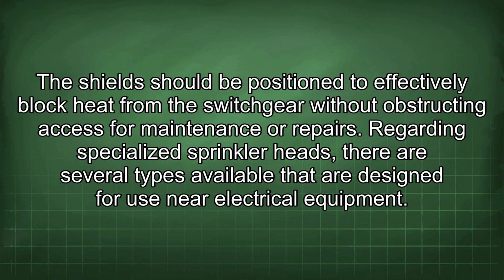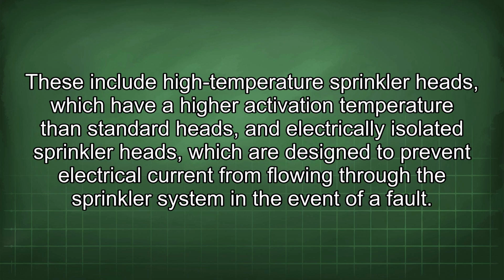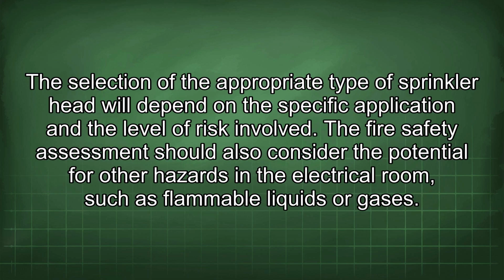Regarding specialized sprinkler heads, there are several types available that are designed for use near electrical equipment. These include high-temperature sprinkler heads, which have a higher activation temperature than standard heads, and electrically isolated sprinkler heads, which are designed to prevent electrical current from flowing through the sprinkler system in the event of a fault. The selection of the appropriate type of sprinkler head will depend on the specific application and the level of risk involved.